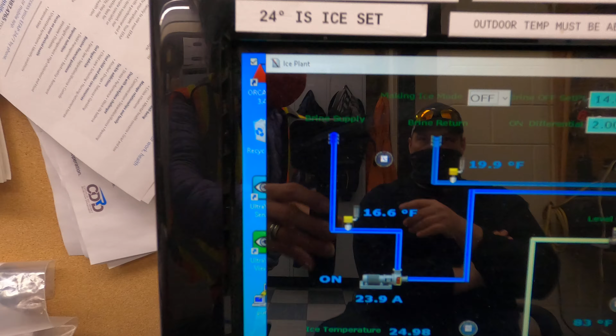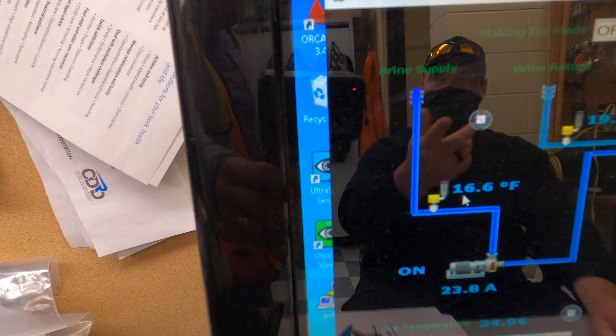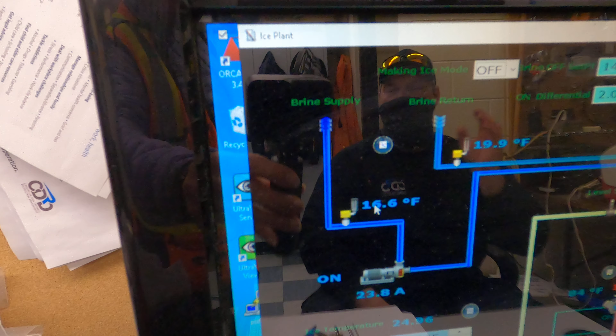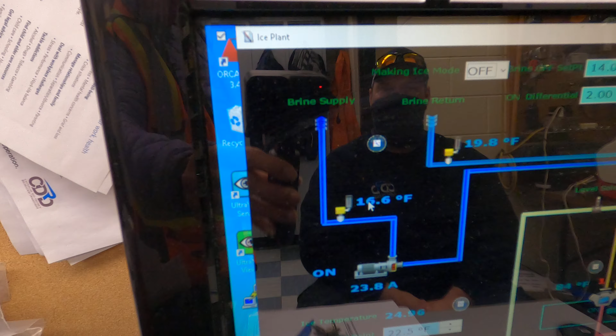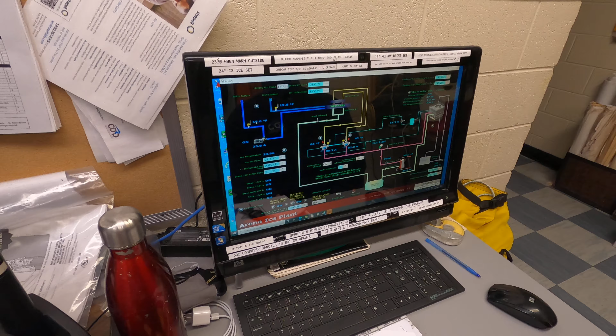So it's picking up about 4 degrees from the atmosphere. Well, on this side, so on a world that when it goes out to the rink, leaving the chiller at this temperature, and then when it comes back from the floor to the chiller, it's gaining that much. And then you can look at it the same way, well, it just came from the floor at this temperature, so it's actually losing that much temperature to the chiller. Right, I see. Right, that's the way you're looking at it. Right? I always look at it from what it's releasing going to the rink and absorbing back. Right, gotcha. Yeah, what I'm absorbing in the rink. Right. Because that's the biggest thing.